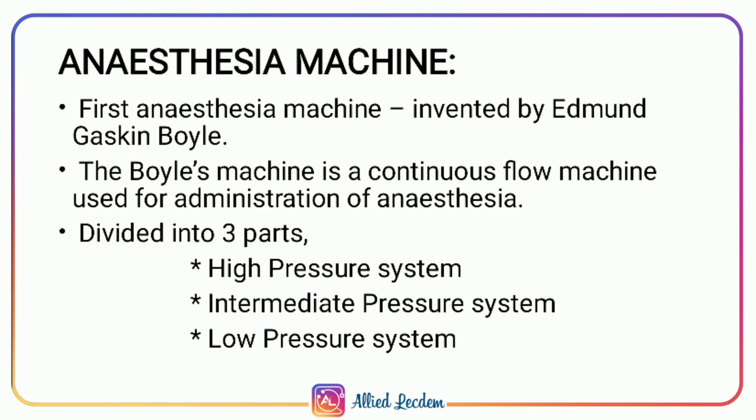The anesthesia machine is an important medical device used to generate and mix fresh gas flow of medical gases such as oxygen, nitrous oxide, and air with inhalational anesthetic agents for the purpose of inducing and maintaining anesthesia. Other names for the anesthesia machine are the anesthesia workstation or anesthesia delivery system. The first anesthesia machine was invented by Edmund Gaskin Boyle, hence it is called the Boyle's machine.